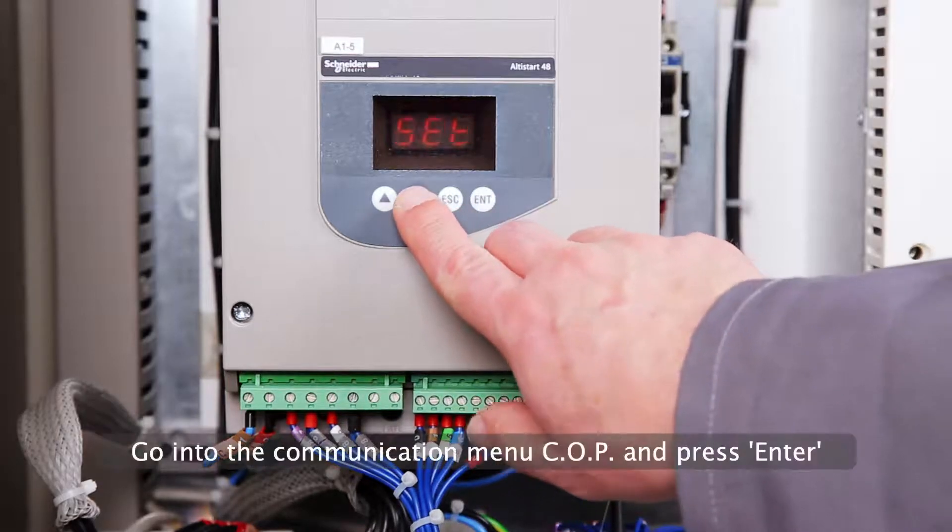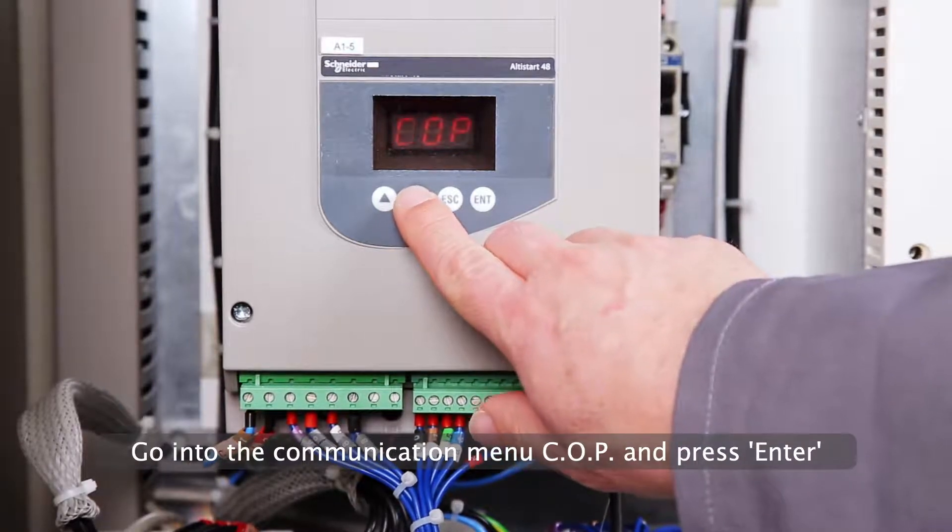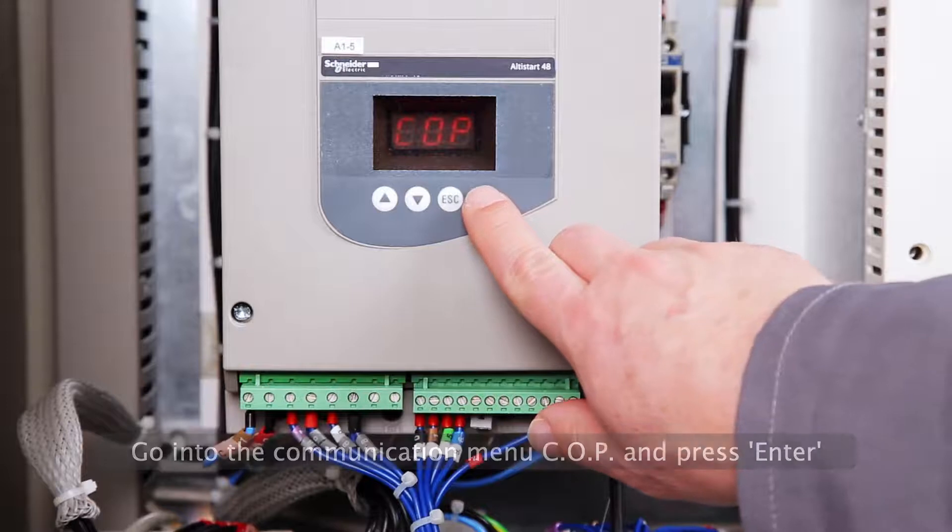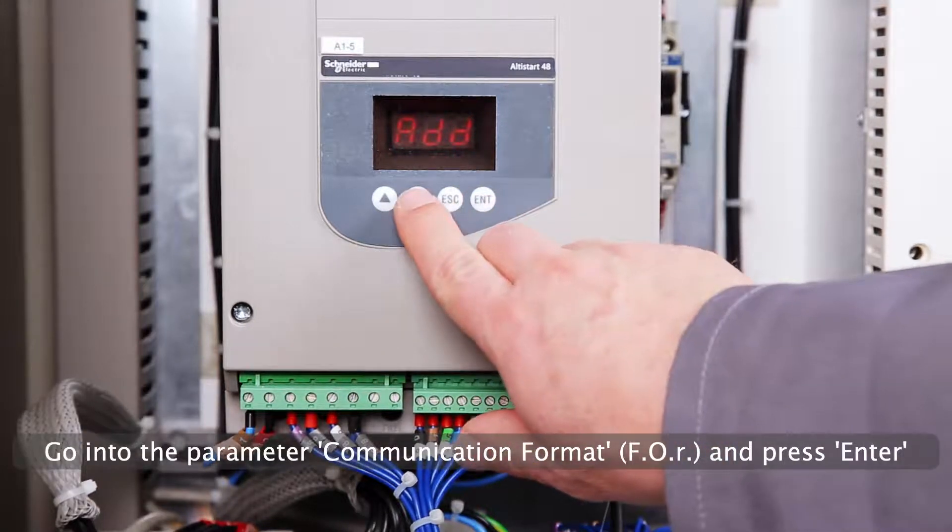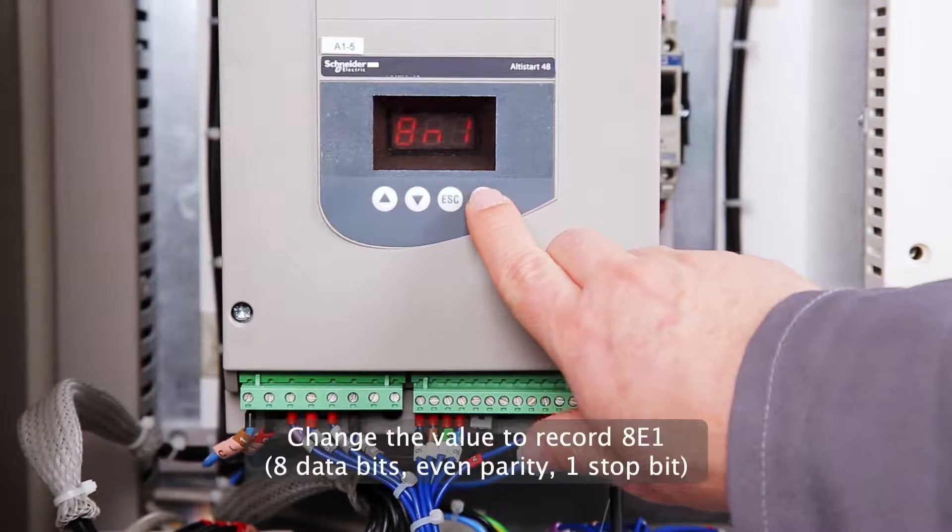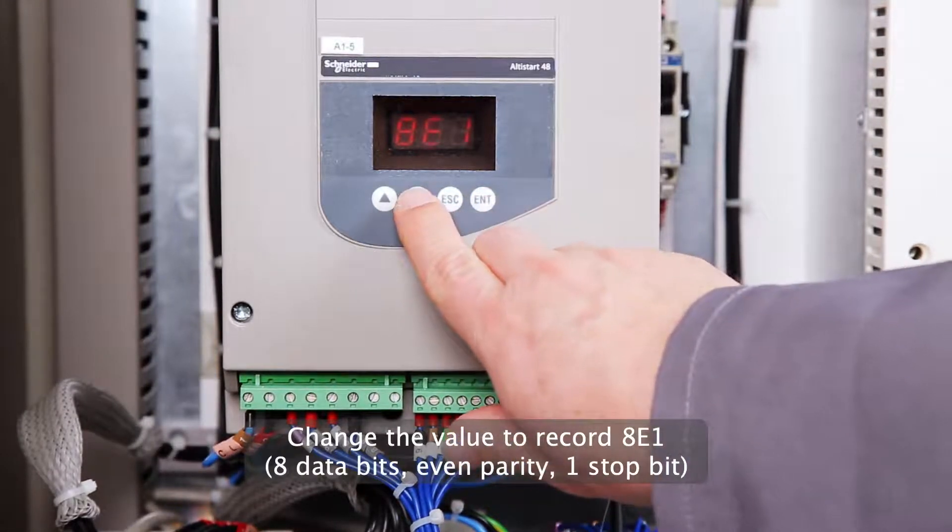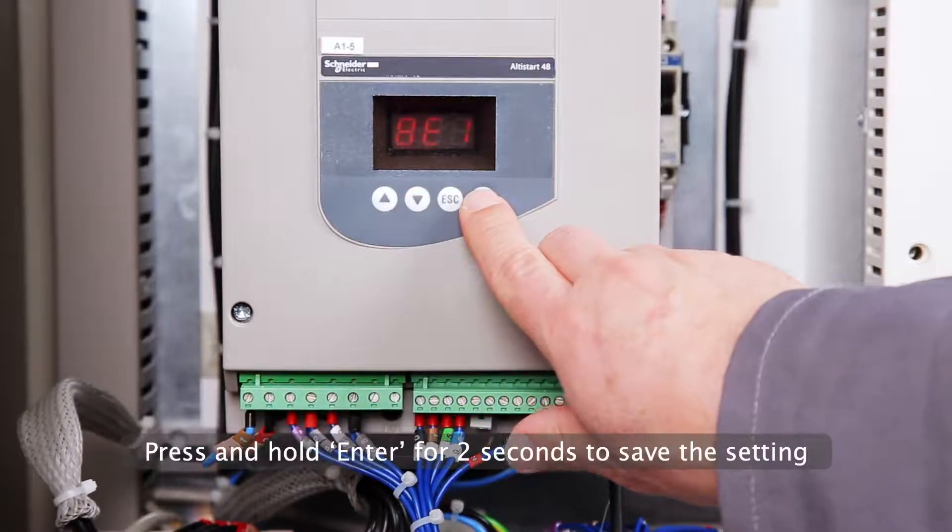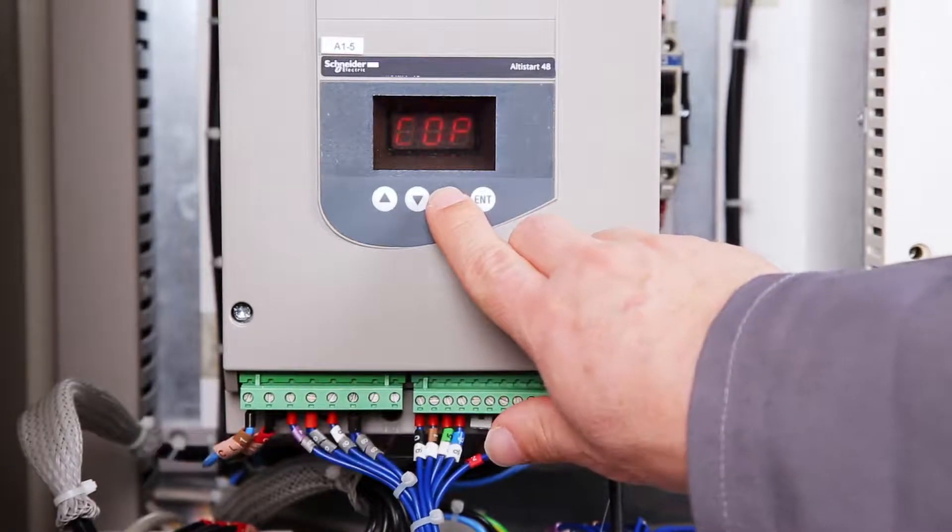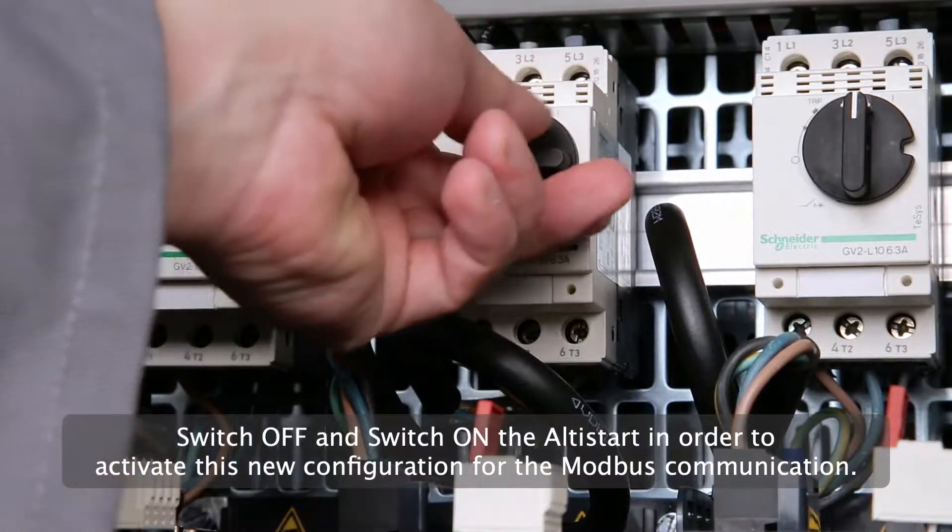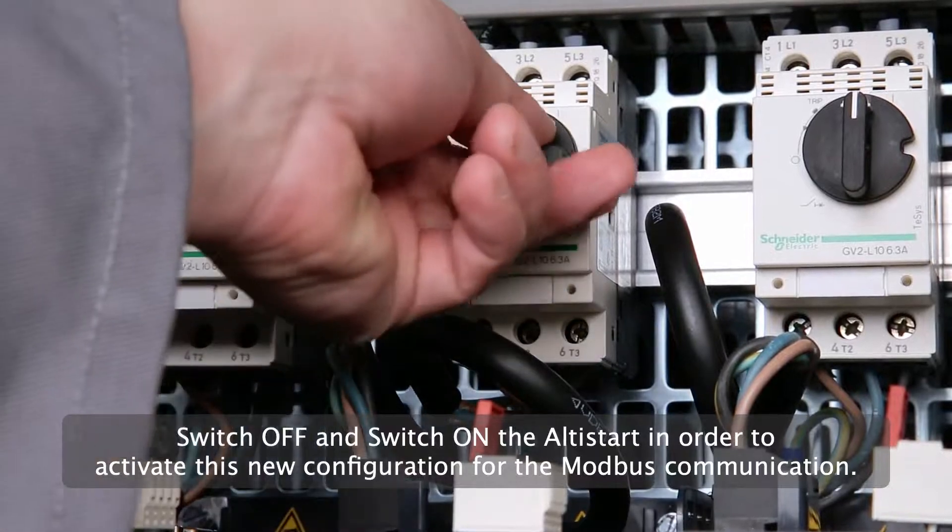Go into the Communication menu COP and press Enter. Go into the parameter Communication Format and press Enter. Change the value to record 8E1. Press and hold Enter for 2 seconds to save the setting. Switch off and switch on the Altistart in order to activate this new configuration for the Modbus communication.